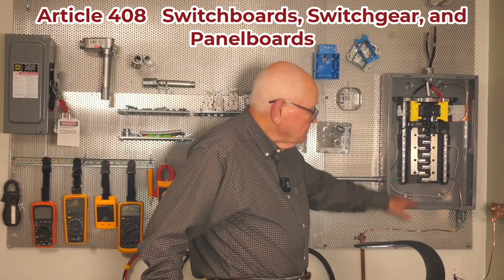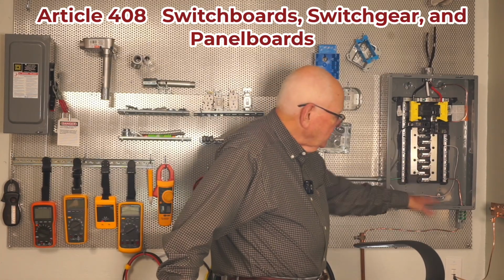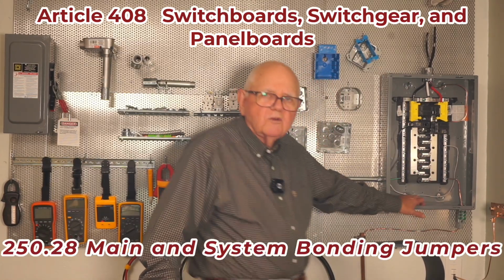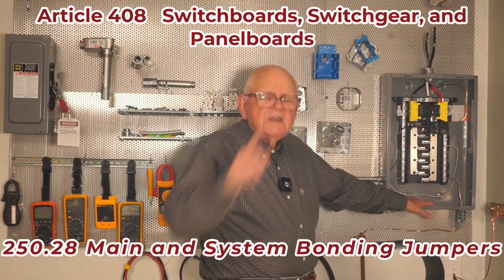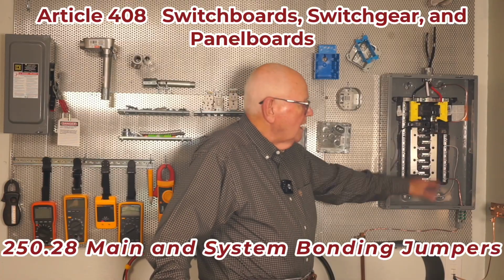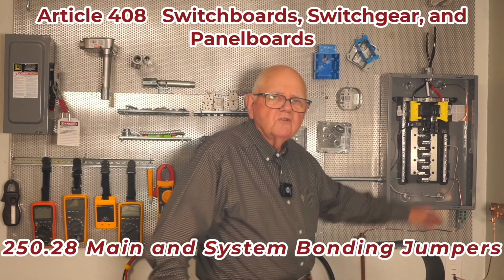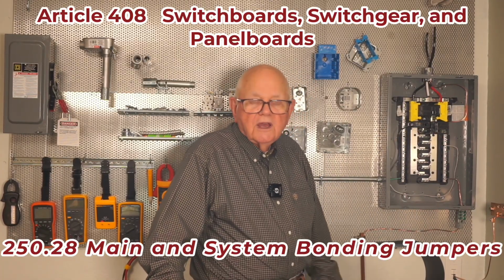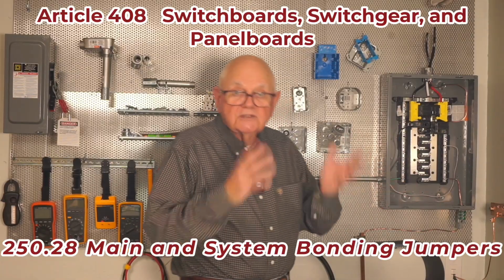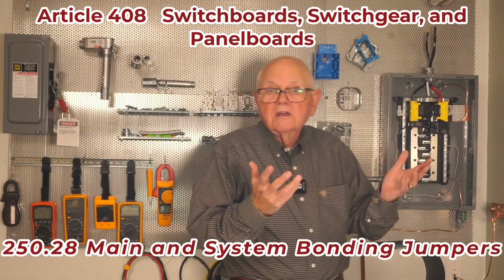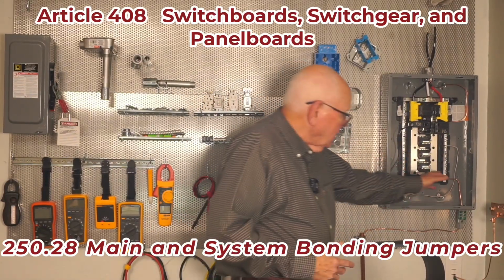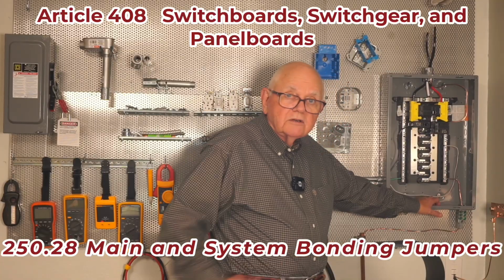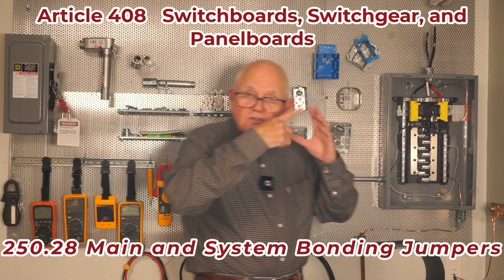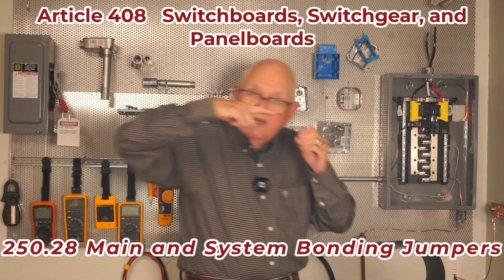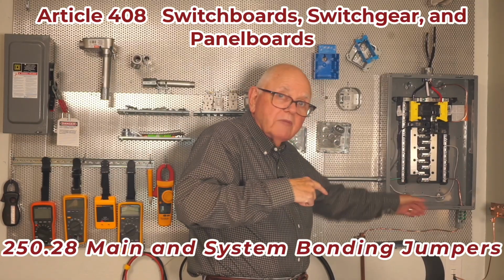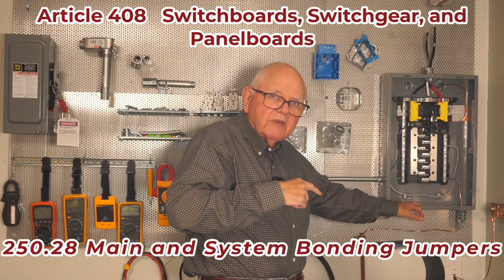That's good. But this particular panel board tells me on one of my labels that it's suitable as service equipment. That means that when I buy it, it comes with a main bonding jumper. That's the green screw over here on the neutral bus. When I buy it, that screw is probably not screwed in, and the neutral bus is insulated from the metal enclosure. But when I screw that screw in, it goes through the neutral bus and makes contact with my metal enclosure, bonding it to the enclosure.